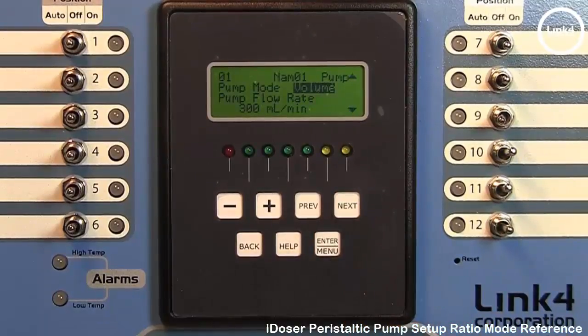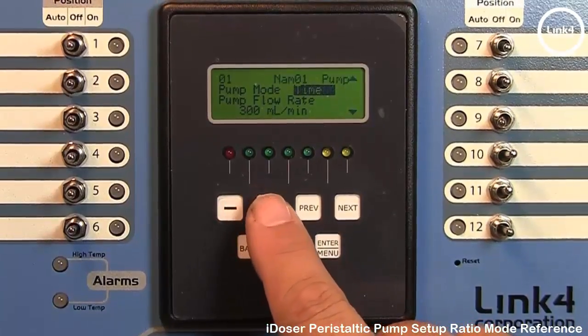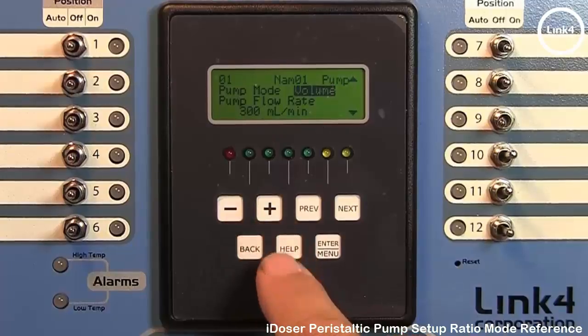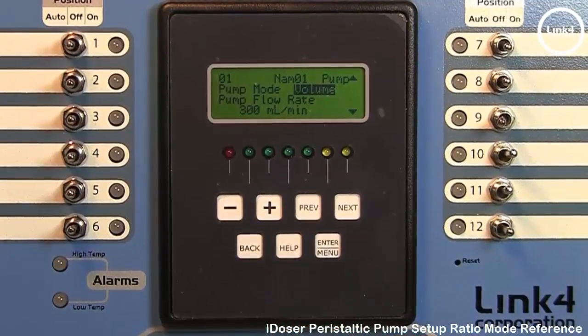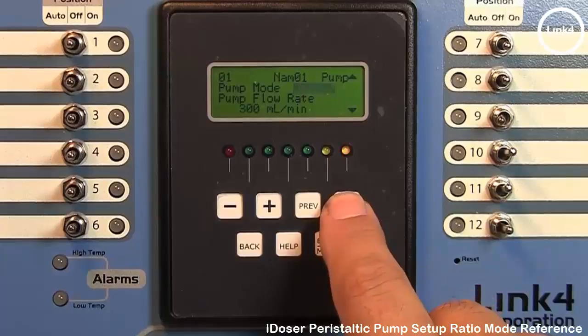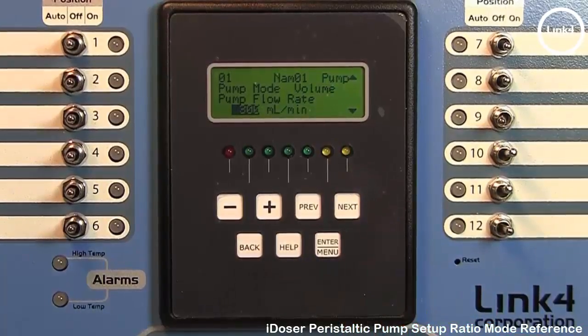Now there are 2 types of pump modes. There's volume or time, and to toggle between the two, you would simply hit the plus button or minus. And we want to use the volume setting. Hit next. And we come to pump flow rate.